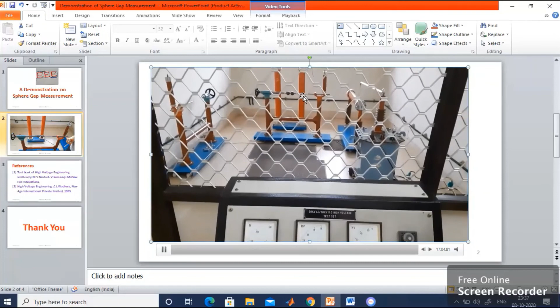Similarly, you need to repeat the step for the sphere gap equal to 10 millimeters, 15 millimeters, and 20 millimeters. Tabulate all the readings and compute the accurate value of breakdown voltage. Finally, plot the breakdown voltage versus the gap distance; you should get a straight line curve. This is what you are supposed to do.